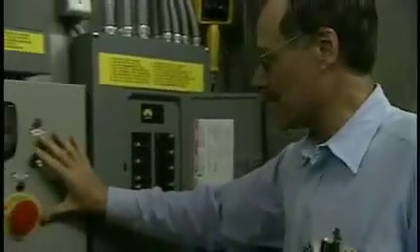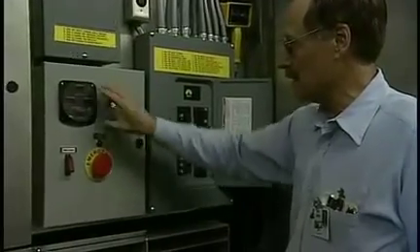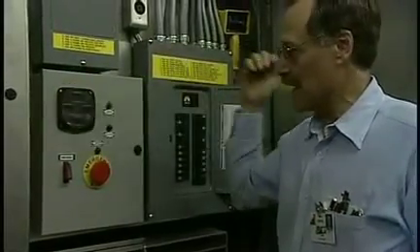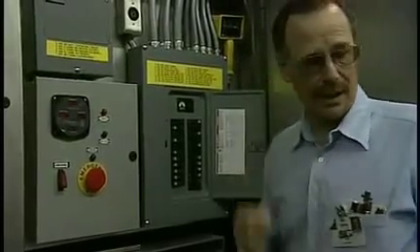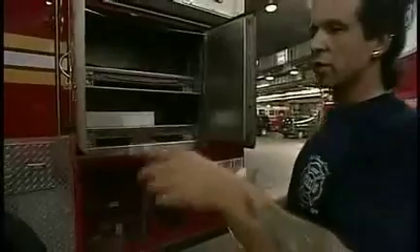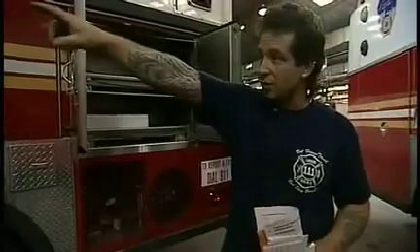This is a control box for the generator — it's a hydraulically controlled generator. This is an emergency stop, obviously. We can measure the power and frequency of the generator for normal operation. The generator is actually mounted at the back of the truck, in that compartment that's open back here — that's where the hydraulic generator is located. It's a hydraulic generator that runs off a PTO driven from the transmission. The transmission drives the PTO, which makes hydraulic pressure and turns this unit back here, generating electrical current. It's channeled back through that control panel and then goes out to various outlets, like this one here.